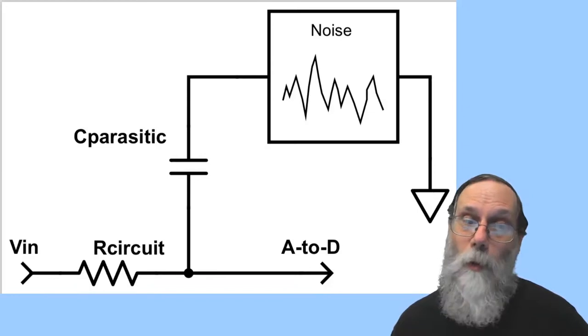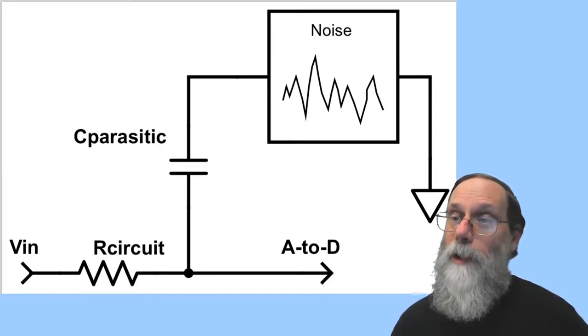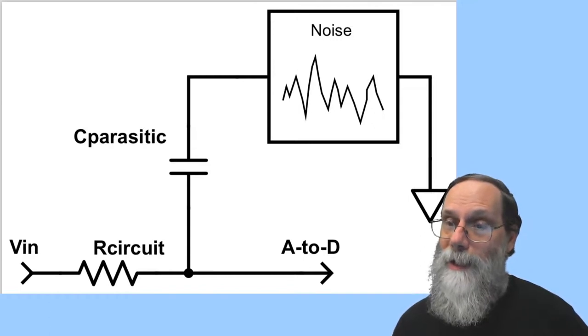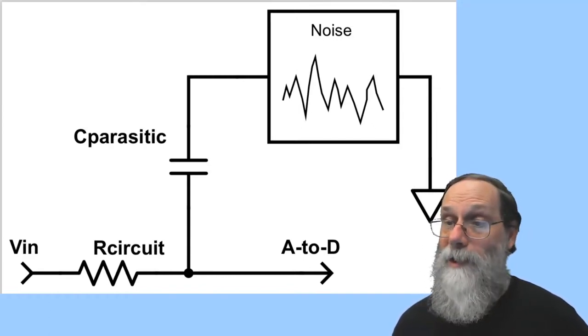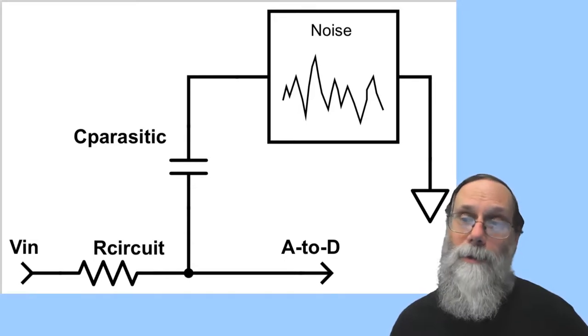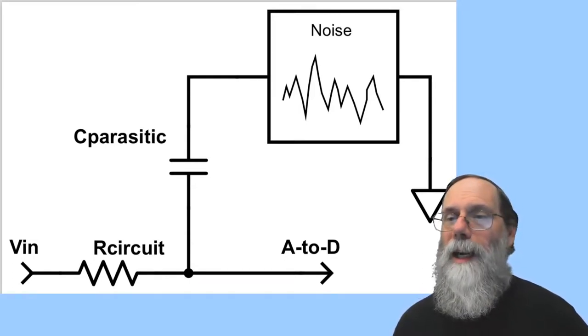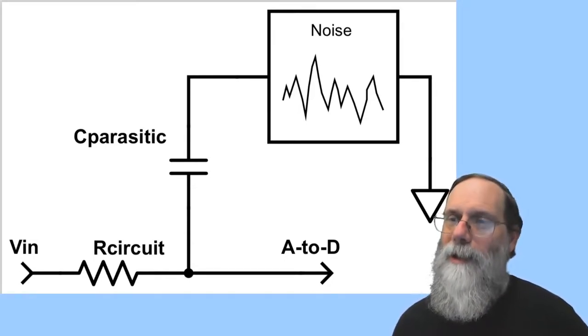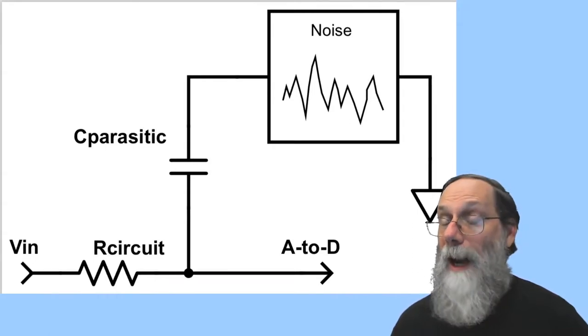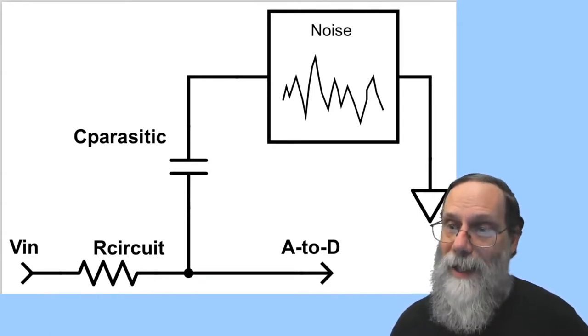And that what you're seeing is that there's a sample and hold on the analog-to-digital converter. And if you don't put a new signal in, it's still going to have some of the old signal from the previous channel. So what you're seeing on the instrument isn't always what's there outside. It has some memory and stuff.